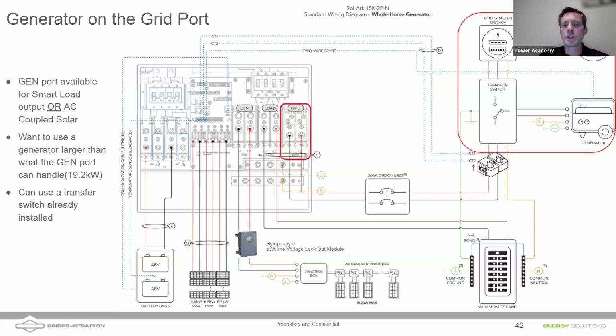And so what we can do here is we can install a lockout module. So if you're using a Symphony 2 or a Symphony Choice transfer switch from Briggs and Stratton, this lockout module, which goes for just a little over $100, I think, you can include so it turns off the AC coupled solar when the generator turns on. As long as that AC coupled solar is big, there shouldn't be that many cases where the batteries get drained while the AC solar is pumping, right? But it can happen if you've got a small AC coupled array feeding in. So with the use of this lockout module, you can still put a generator in on a system. So great question.